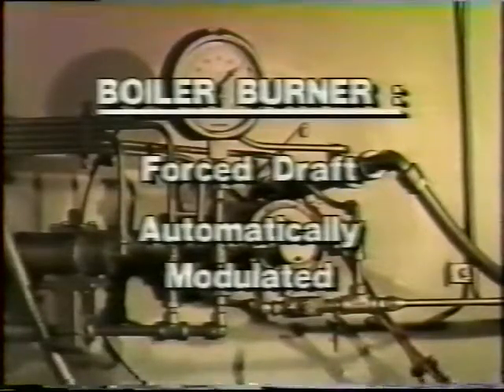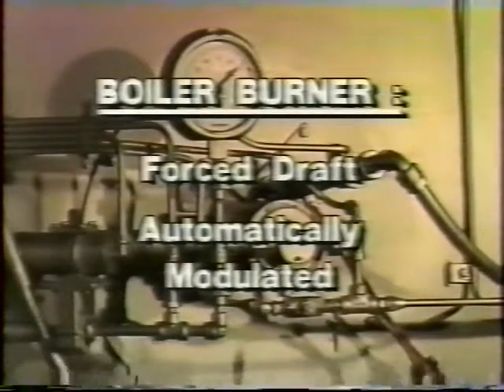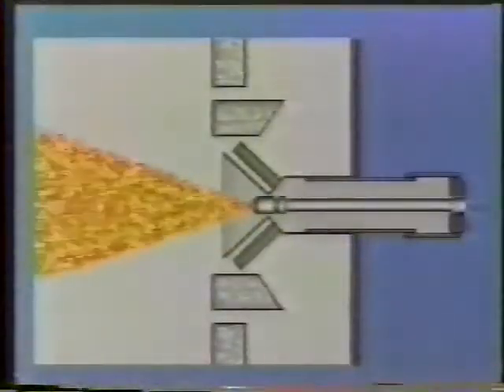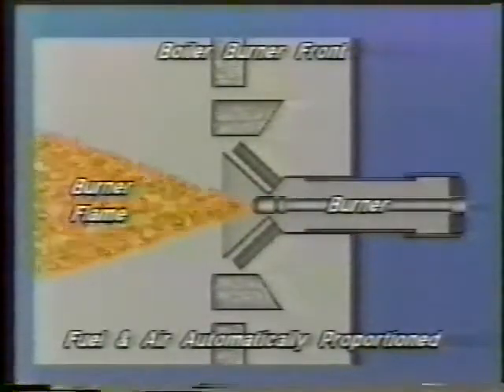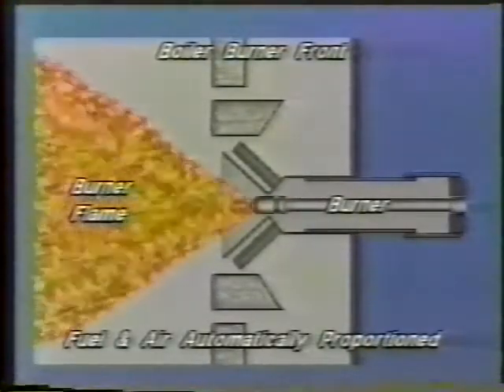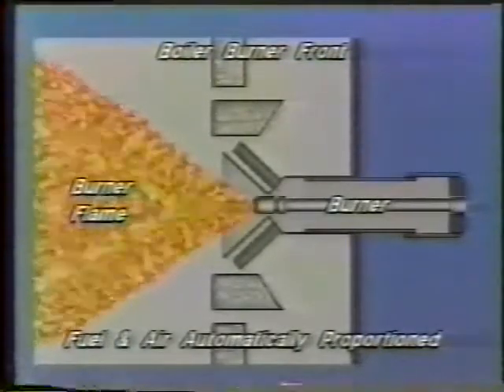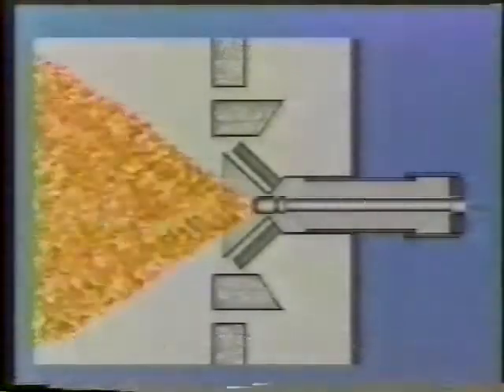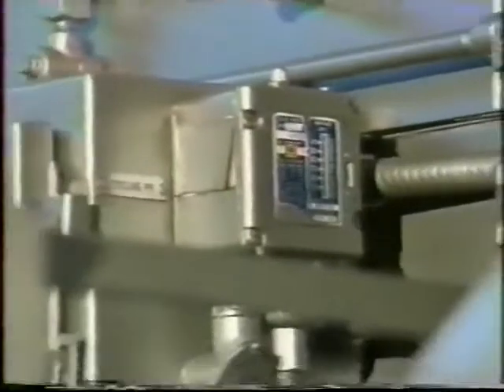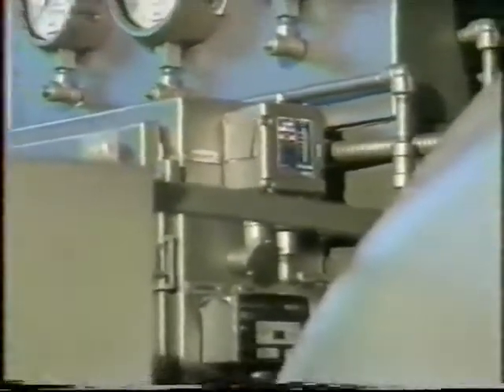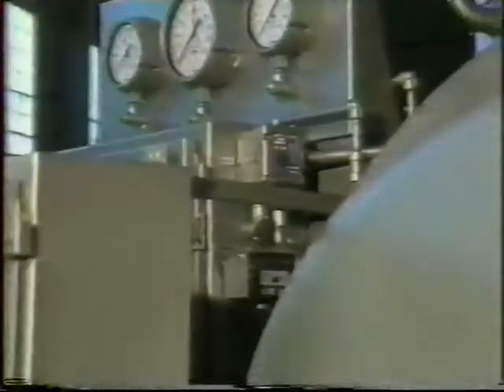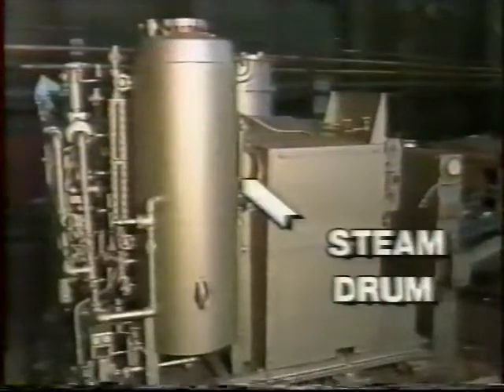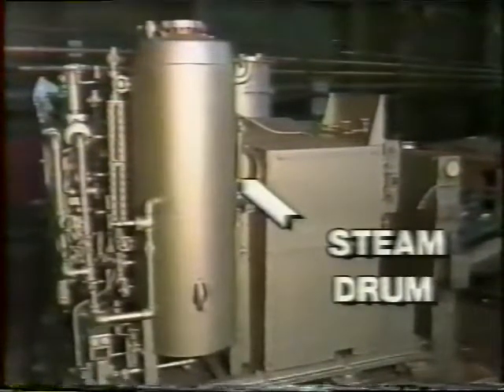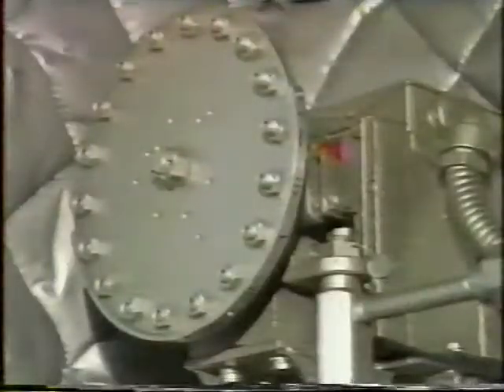The burner of this boiler is a forced draft automatically modulated type. Fuel and combustion air are automatically proportioned to each other over the complete burner range in response to variations in steam pressure by a variable type pressure element control. The control senses the steam load, or pressure in the steam drum, then automatically causes the firing rate to be adjusted through the modulating burner control.